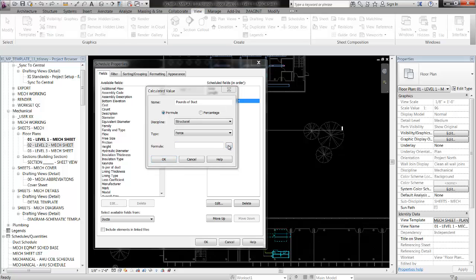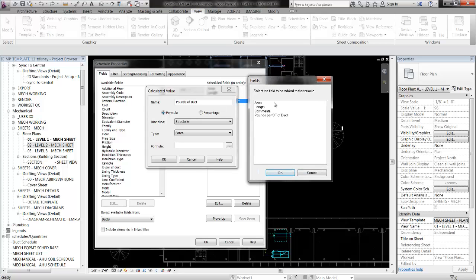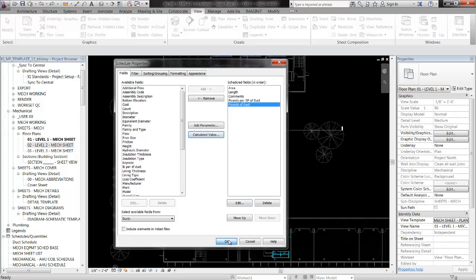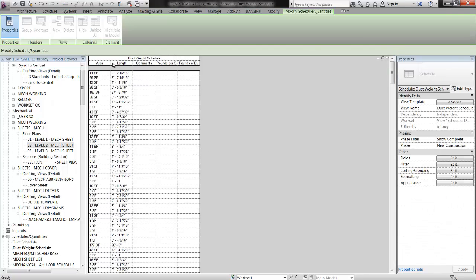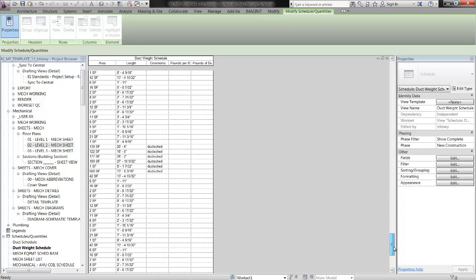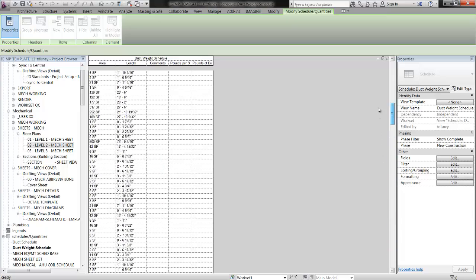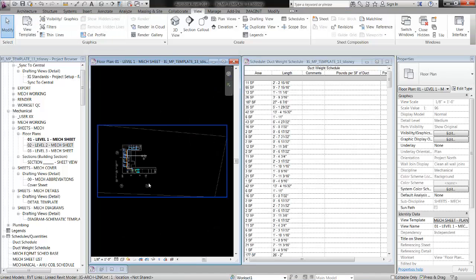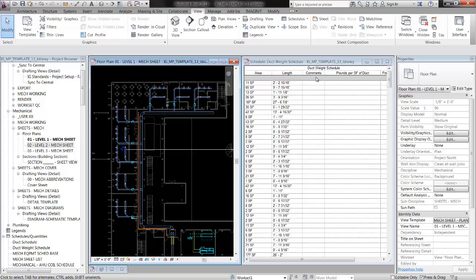Hit the ellipsis sign and you get a window which lets you select from the parameters you already have. That's going to be area of duct, then type in asterisk for times, and then select 'pounds per square foot of duct.' Hit OK. There's more work we need to do on the schedule, but let's just start it to see what we get. We have a lot of pieces of duct in this project — it's a pretty long and painful schedule to look at, pulling in every single straight piece of duct work in the entire project.